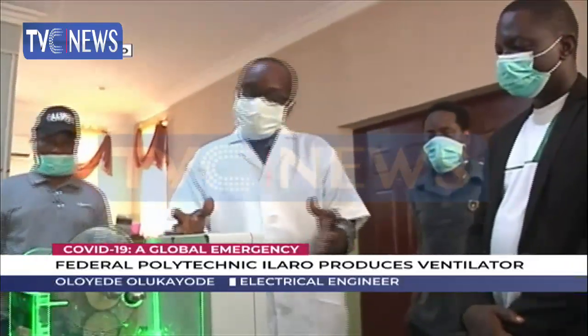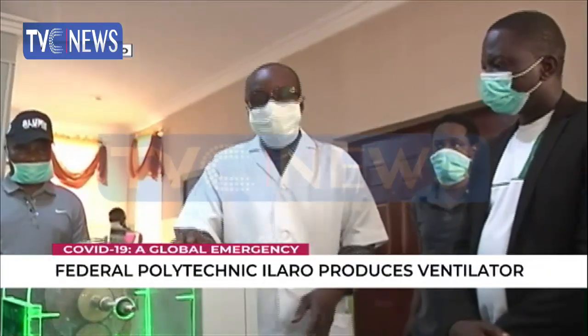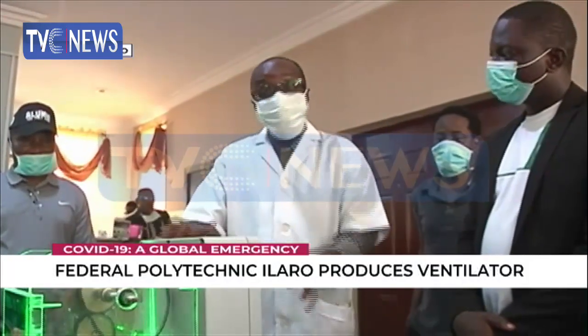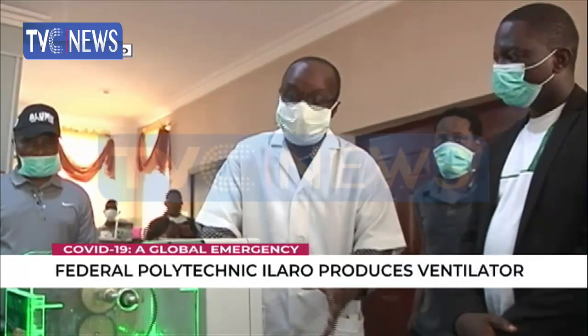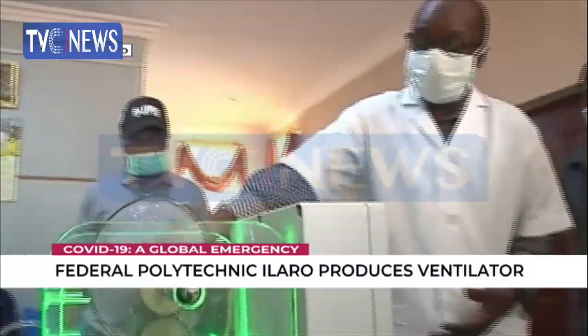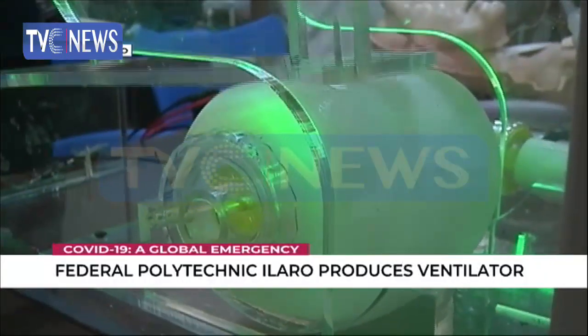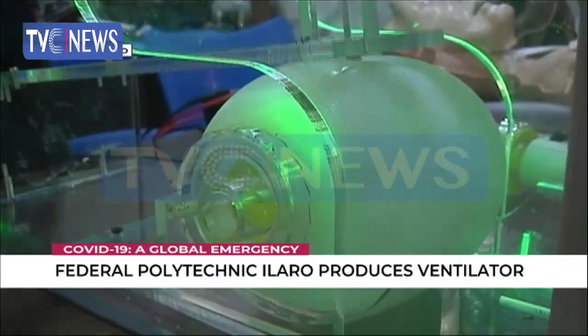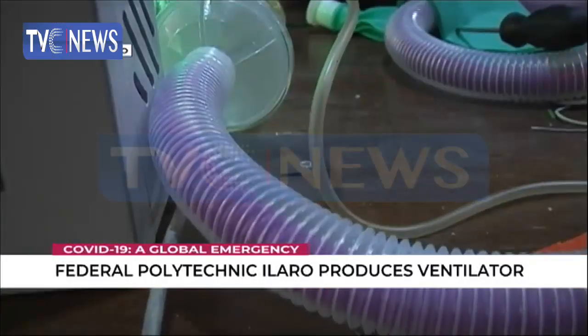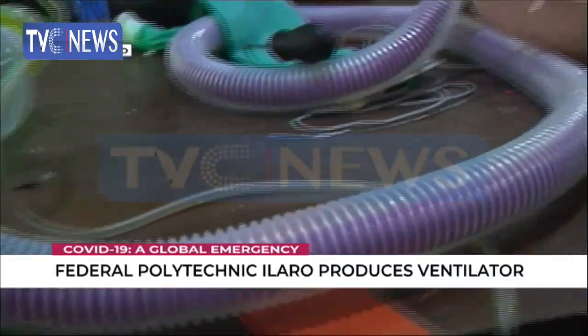The system is an electromechanical device. Because of its complexity, it uses discrete electronic components with various voltages working for different parts of the system. The embedded system operates on a very low voltage. There is an electric motor, a display, and an ambu bag through which air or oxygen is delivered to the patient. The ambu bag is connected to the airway tubing.